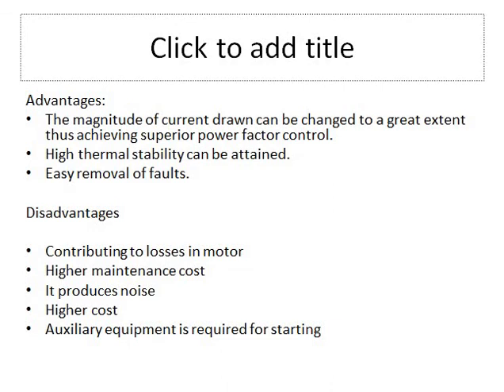Now, what are some of the advantages of the synchronous condenser? To begin with, first and foremost, the magnitude of current drawn can be changed to a greater extent, thus achieving superior power factor control. Further, thermal stability can be attained, and it's easy to remove faults.